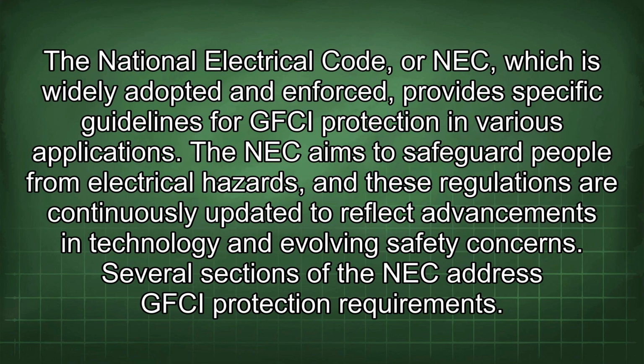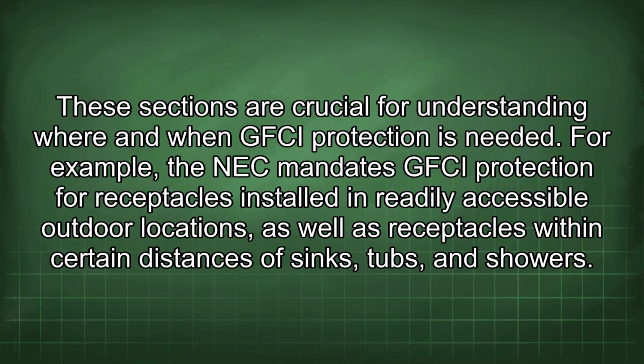The National Electrical Code, or NEC, which is widely adopted and enforced, provides specific guidelines for GFCI protection in various applications. The NEC aims to safeguard people from electrical hazards, and these regulations are continuously updated to reflect advancements in technology and evolving safety concerns. Several sections of the NEC address GFCI protection requirements. These sections are crucial for understanding where and when GFCI protection is needed. For example, the NEC mandates GFCI protection for receptacles installed in readily accessible outdoor locations, as well as receptacles within certain distances of sinks, tubs, and showers.